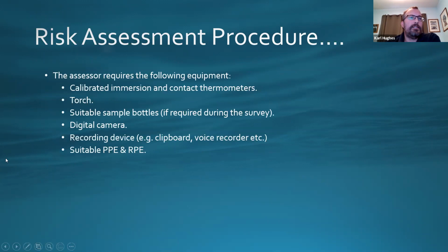So just a few things on what you need when doing a risk assessment. Obviously you need to make sure your thermometer is calibrated. The ones we have get calibrated annually, just to make sure the accuracy of the results is there. Like I said previously, there was a thermometer I'd seen on one site showing 12 degrees throughout the whole year, when really on cold water you'd expect it to be a lot colder in winter months than in summer months. So that's a red flag straight away that something's not quite right with the equipment. Make sure it's calibrated and kept up to date.